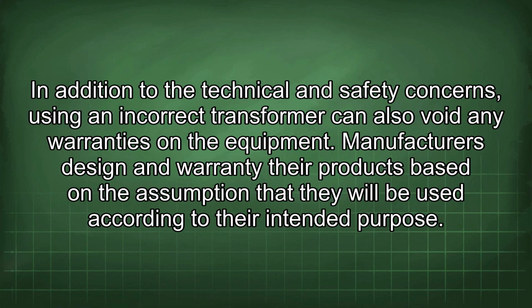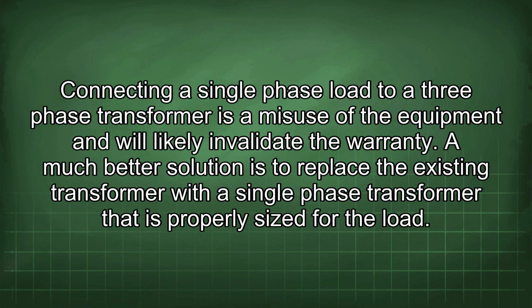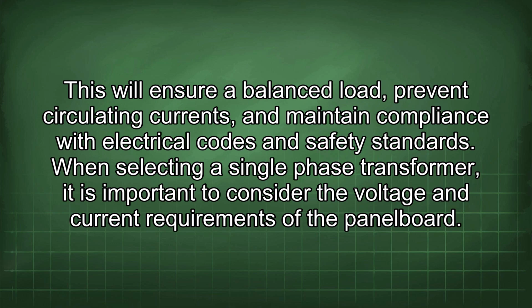In addition to the technical and safety concerns, using an incorrect transformer can also void any warranties on the equipment. Manufacturers design and warranty their products based on the assumption that they will be used according to their intended purpose. Connecting a single-phase load to a three-phase transformer is a misuse of the equipment and will likely invalidate the warranty. A much better solution is to replace the existing transformer with a single-phase transformer that is properly sized for the load. This will ensure a balanced load, prevent circulating currents, and maintain compliance with electrical codes and safety standards.